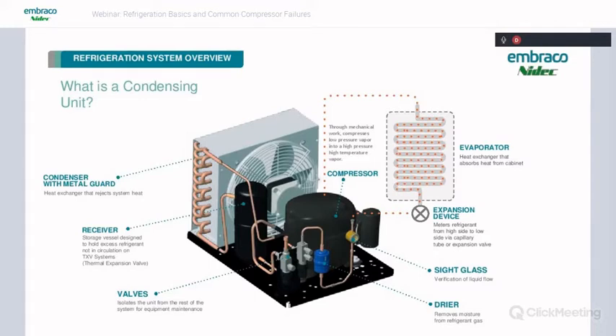And typically, a lot of your condensing units nowadays have service valves to isolate the system for service. And then you're also seeing a lot of the dryer and the sight glass already mounted on the system. So basically, beyond that, your liquid coming out of the condenser is going to go to the evaporator, and that's where the expansion device is going to be. So basically, it's the whole high side of the system.